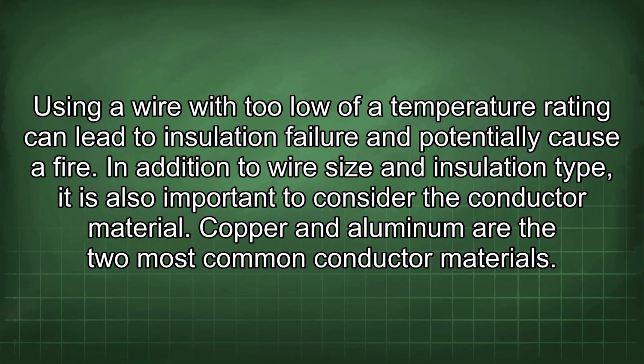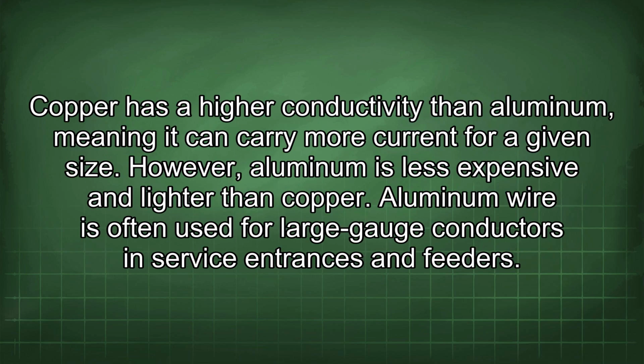In addition to wire size and insulation type, it is also important to consider the conductor material. Copper and aluminum are the two most common conductor materials. Copper has a higher conductivity than aluminum, meaning it can carry more current for a given size.